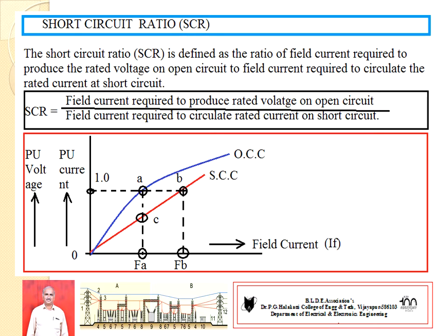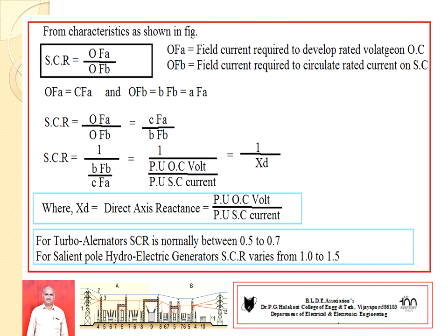OFB is the field current required to develop the rated current under short circuit conditions, meaning all three terminals of the alternator are shorted. So OFA is the field current to develop rated voltage on open circuit, and OFB is the field current to develop rated current at short circuit. Therefore, SCR = OFA / OFB.